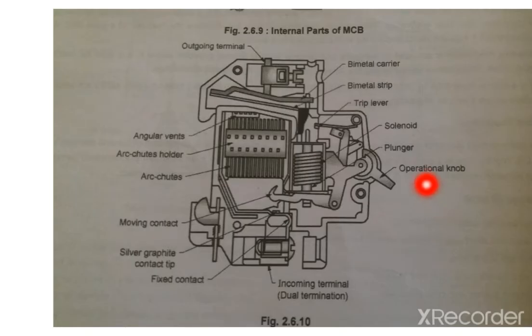This operating knob is provided for the manual operation of the circuit breaker. This trip lever is connected to the operating knob. This gives the signal to the operation, and the outgoing terminal of this MCB is given by this terminal. This is how the construction of the miniature circuit breaker is defined.